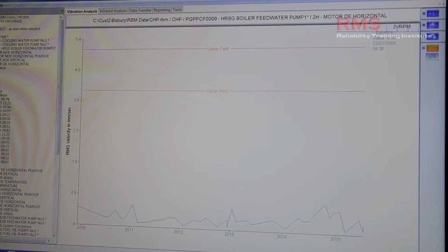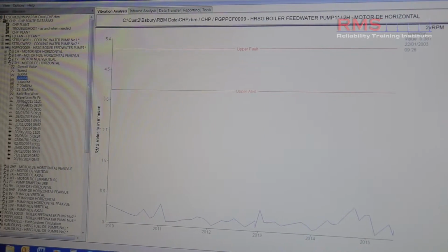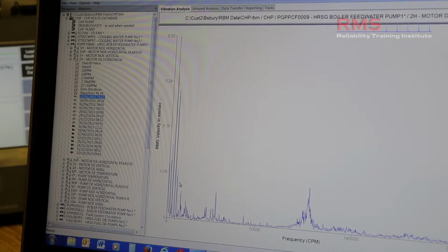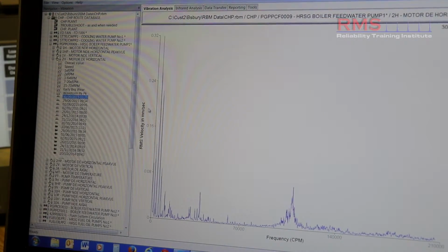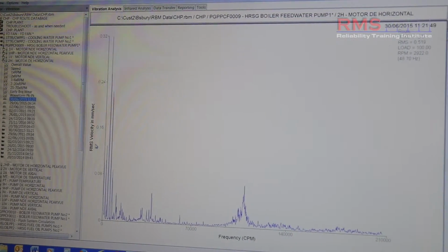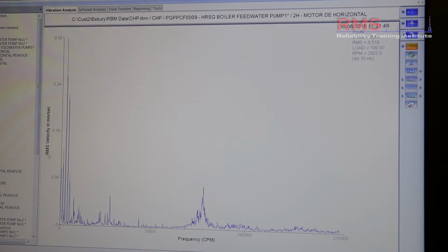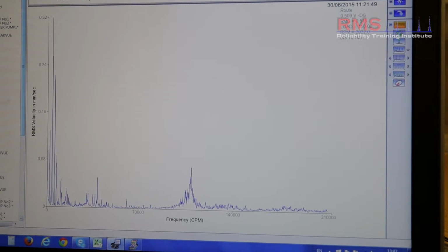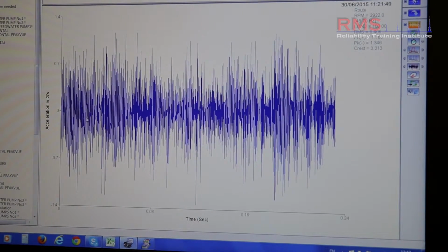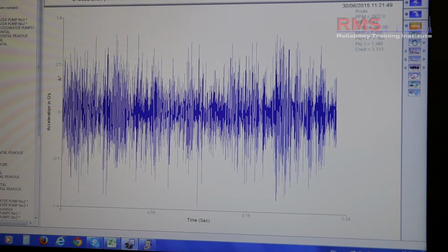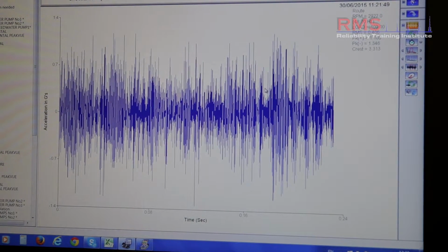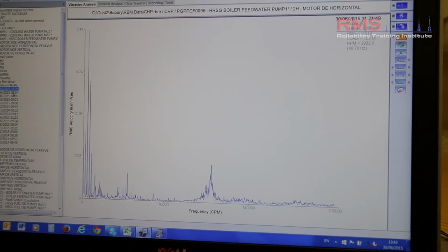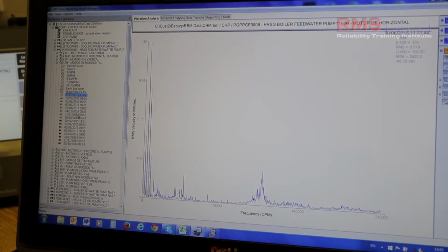If we want to go further because we see a change, we would then turn our attention to the diagnostic data collected here. We've got a spectrum, a velocity spectrum in millimeters per second, or if you're in the US, maybe it's in inches per second. And maybe an RMS value is more common for an ISO standard. And we've got the time waveform as well from which the spectrum is actually born, maybe a lot more complex, but obviously that's part of the diagnostic information.